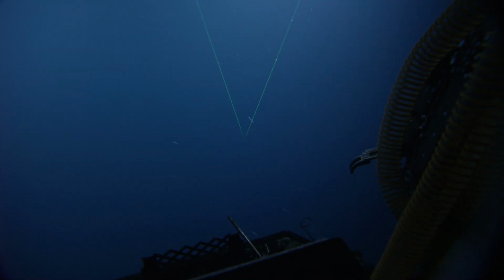I'm a bit hesitant to actually do this because we'll interrupt the data during the nice descent profile. Don't do it. But basically you go configuration, there'll be a green box that says external pump. You click it so it goes red, then you click it so it goes green, then you click OK and it will restart the pump. That's going to be the easiest way for you to check. If that doesn't fix it, then you could ask the pilots to do a hard power cycle, and if that doesn't fix it, call me. But it's not going to get that high on a dive like this.